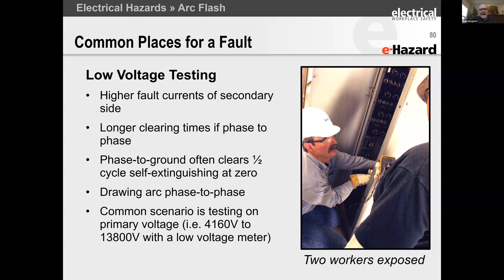So it's really important that you use the test equipment correctly and you have training. Our work standards require annual training recertifications on meter use for workers to make sure they really understand how to do that. These are your meter standards in IEC. We use these same standards. We have a UL equivalent in the US, and typically you're going to have your IEC 61243-3, which will be your absence of voltage check tool. Make sure it meets that standard and make sure it's high quality. You don't want this thing to blow up if you put it across a higher voltage. We typically try to buy a tool that can take 5,000 volts, so that if it's put across the wrong voltage, it won't blow up. It'll just stop working. But some of the tools that meet that standard are very, very low quality. Some of them are really high quality. I recommend you get a really high quality one.